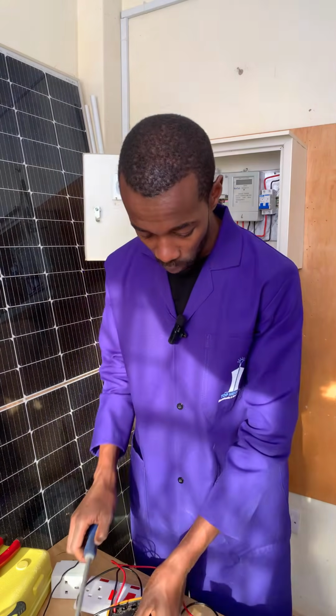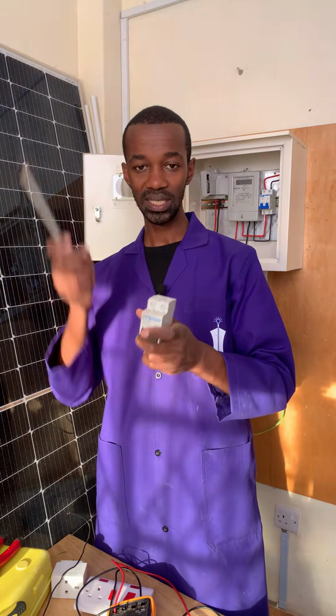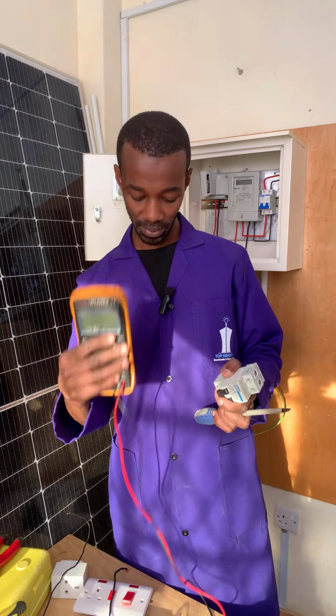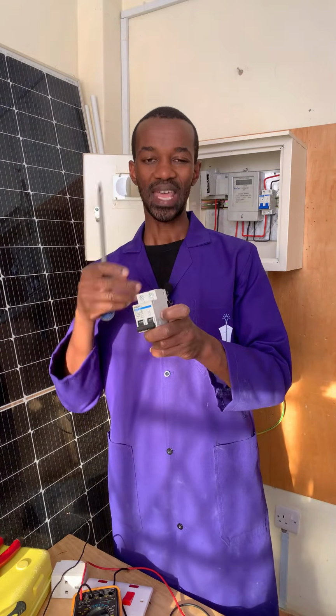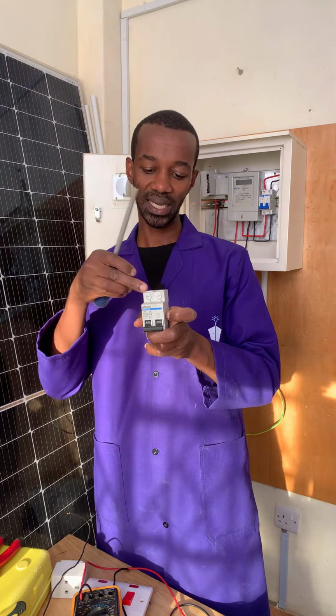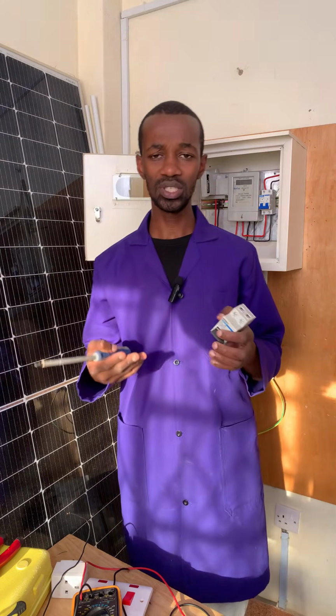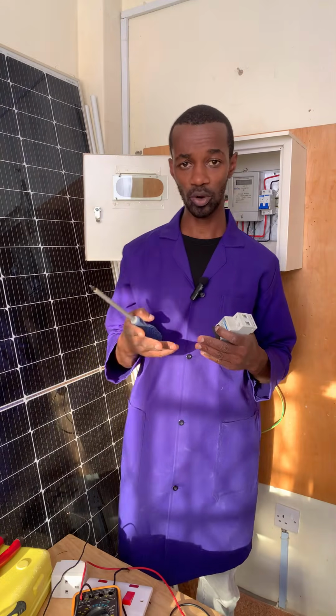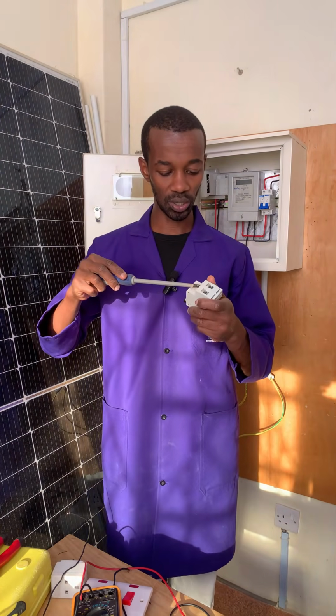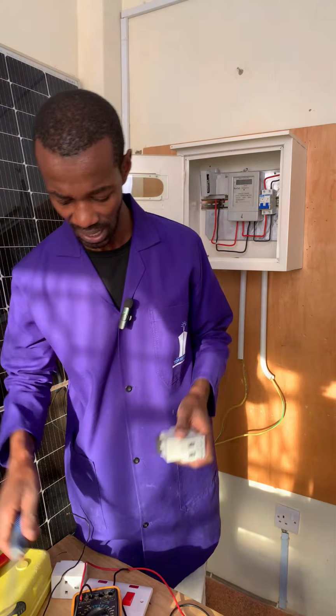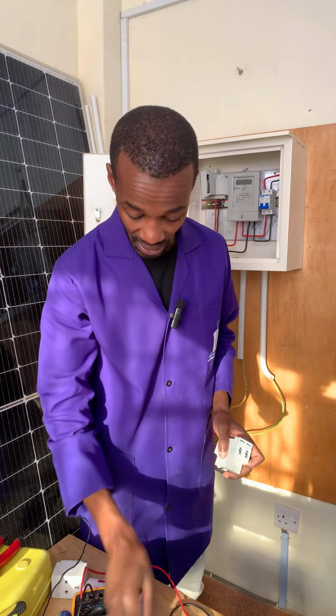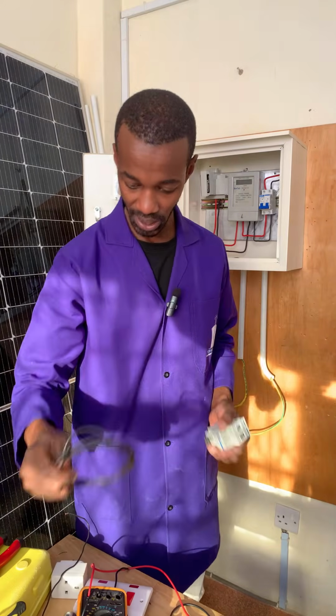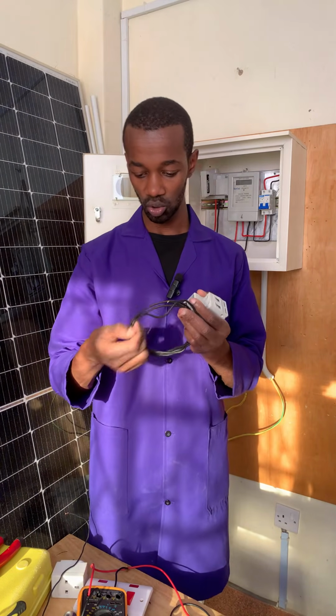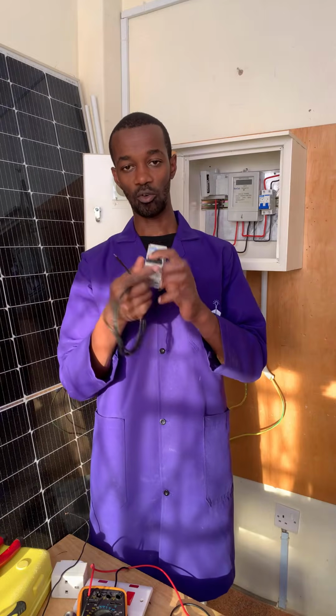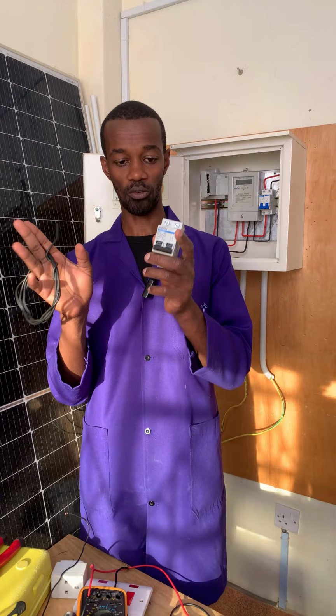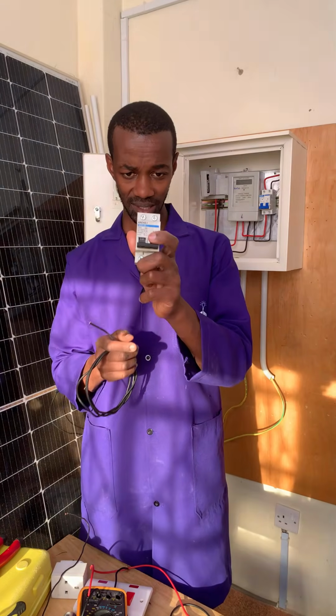So when you get to that consumer unit and you have used your digital multimeter, you test for the voltage, the potential difference across the terminals. Now, if you still get an under voltage at that point, it means there could be a loose connection at the double pole, so you tighten it. Sometimes you even remove that main cable, especially the neutral. You remove the neutral, but make sure that for all your troubleshooting, power is switched off, especially at the double pole.